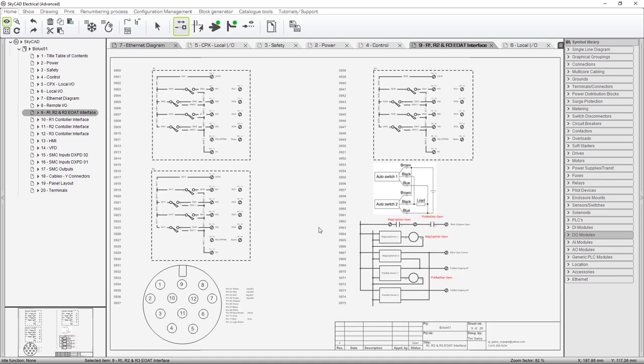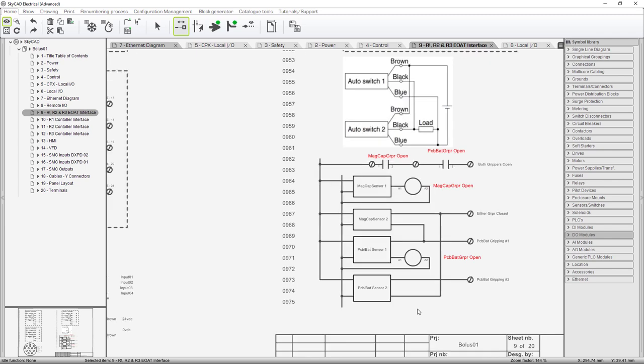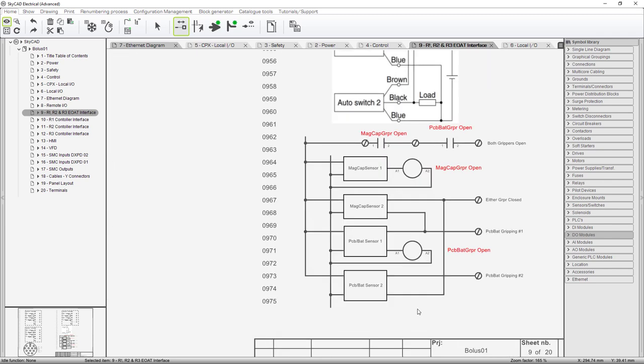On this drawing what I'm showing here is how we are working around the lack of I/O. This is an example right here where we are ORing two sensors together so either one of these sensors auto switch one or two will route power to the load. The load in this case is the input to the robot controller remember it has a robot input one two three and four on each robot. This down here is we are using relays to logically combine some of those sensors. So let's look at what we have here we have four inputs inputs one two three and four. This one is both grippers open, this one is either gripper closed and this one is gripping one and gripping two.